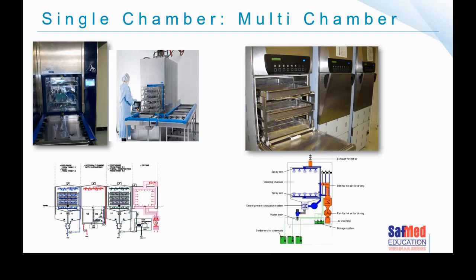The disadvantage of a multi-chamber washer is they are a little bit more expensive and have a huge footprint — they take up a lot of space. And if they go down, you may only have one. Some hospitals, therefore, choose to install multi-chamber washers as well as one single-chamber washer for consistency and continuity of business.